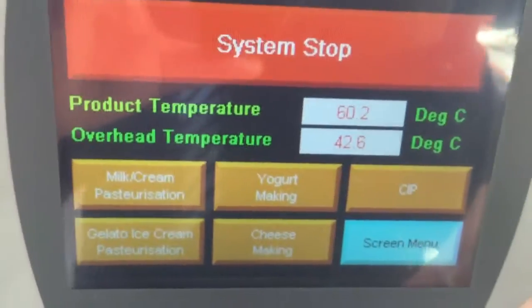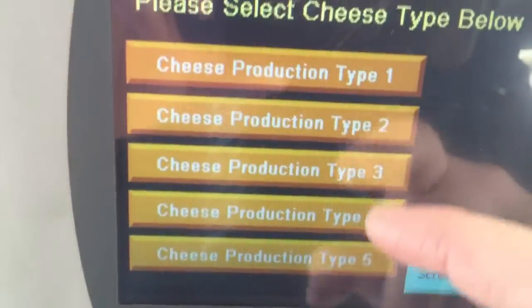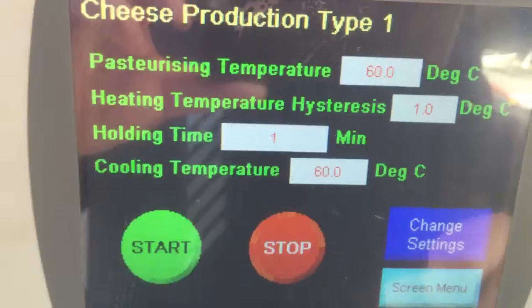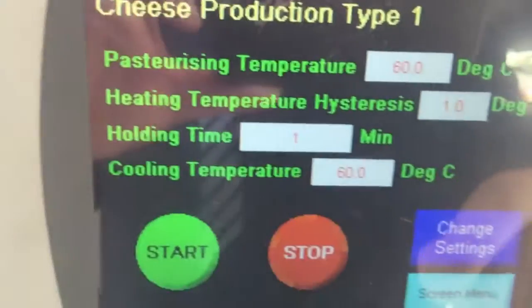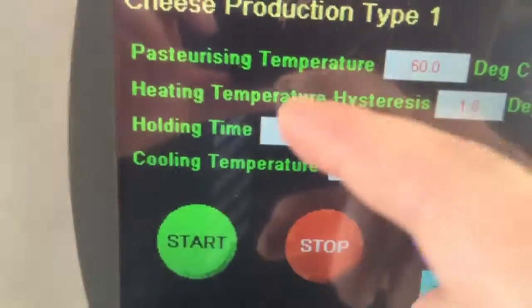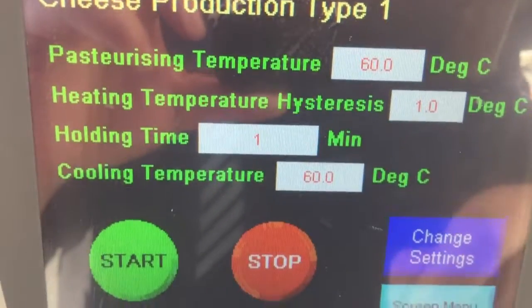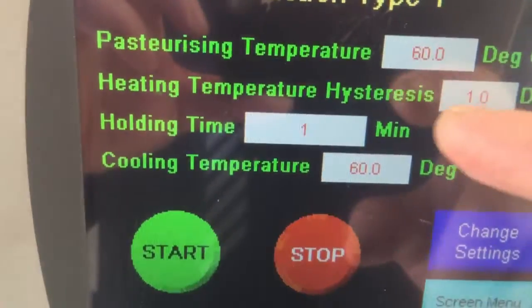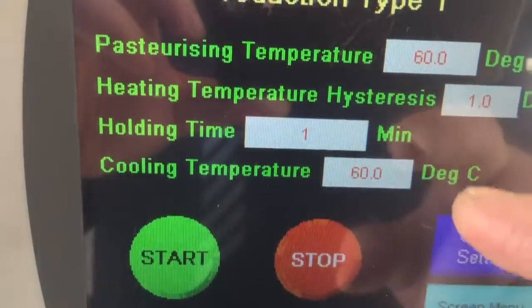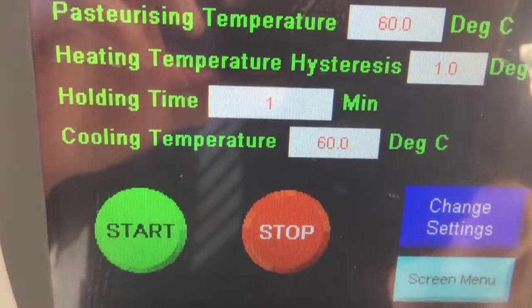In this simulation, we use cheese type 1 for testing. The current temperature is 60.2 degrees, so we set a pasteurizing temperature at 60 degrees, heating hysteresis 1 degree, holding time 1 minute, and cooling temperature to 60 degrees.